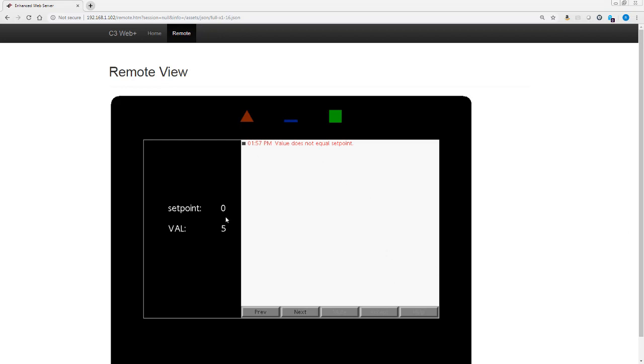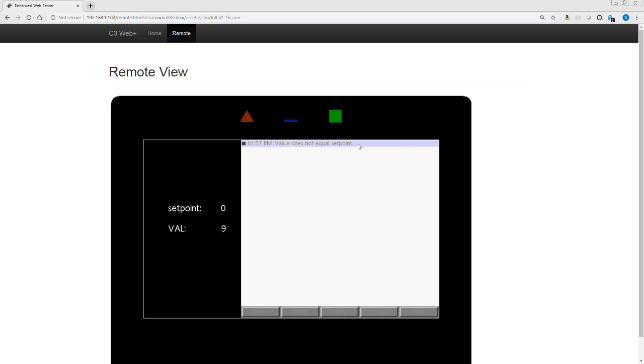When this value does not equal the set point, it is active or red. As soon as it is no longer a live alarm, we saw it turn gray briefly because it's in wait accept mode at that point. If we go ahead and select it and accept it, it will turn olive until it is not true anymore, at which point it will disappear.